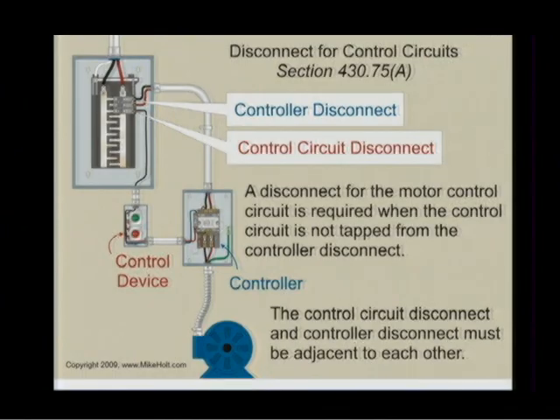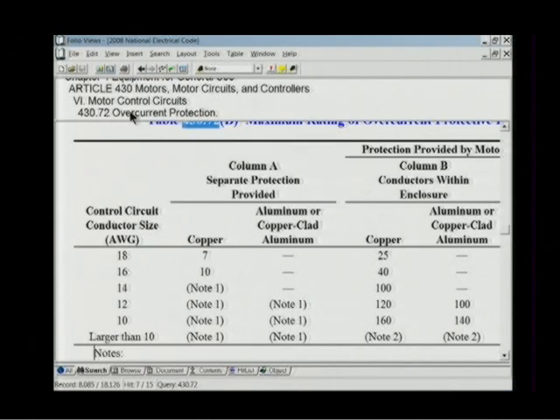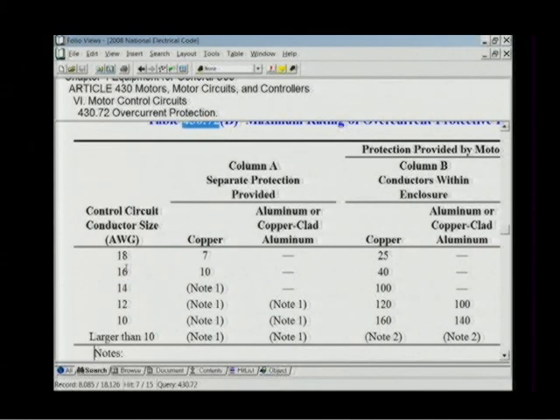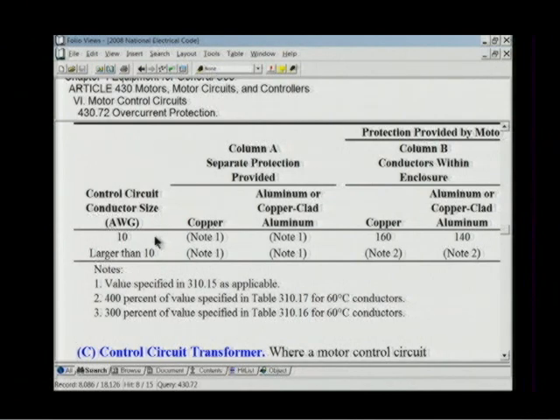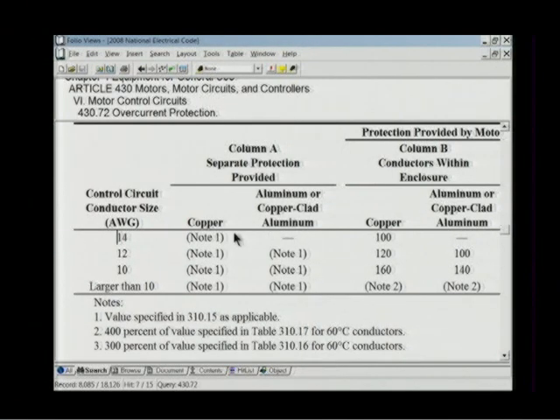And let's go to a graphic right here. Separate protection provided. Well, when you have this scenario, then the code says, if you use 18 gauge wire, provide 7 amp protection. Well, you're not going to get a 7 amp breaker, but you can get a 7 amp fuse. Then you provide 7 amp fuse protection. So not likely for separate protection for that size, but you might do that. 16 gauge wire would be 10 amp. And then note number 1 says, if it's 14 and larger, go to 310.15 as applicable. And when you go to 310.15, it basically tells you to go to Table 310.16.